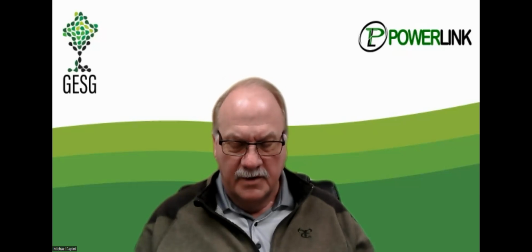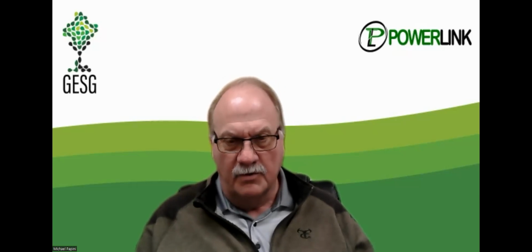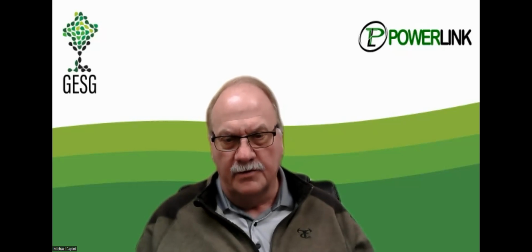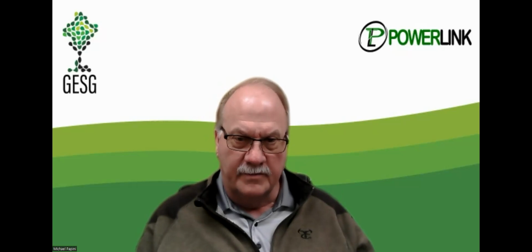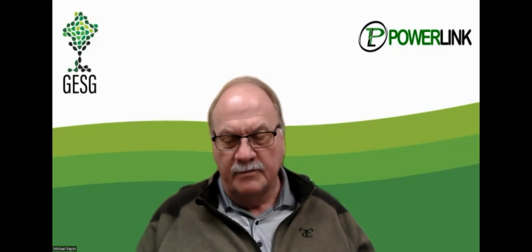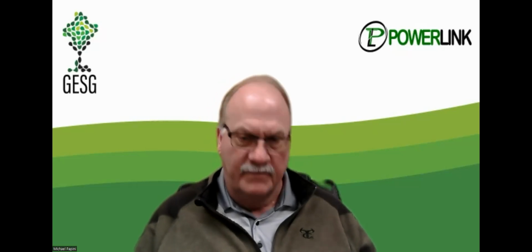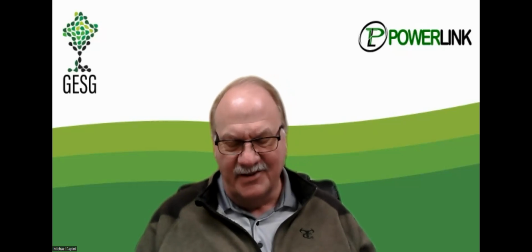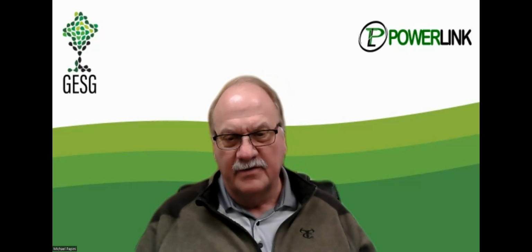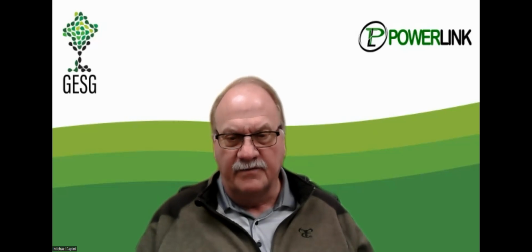But what creates problems with VFDs, LEDs, servo motors, things like that, is they're called nonlinear loads. The nonlinears are all electronics, so they create harmonics on the system, the 3rd to the 13th harmonic. The damaging harmonics are the 5th, 7th, and 11th, which come from VFDs, servos, and LEDs. With that, my boxes, the way I wired them, I also have a patent on it. It's kind of like an active filter, where it'll filter out 90% of the harmonics or the THD in whatever it's hooked to. So it drops a lot of heat off of the system.